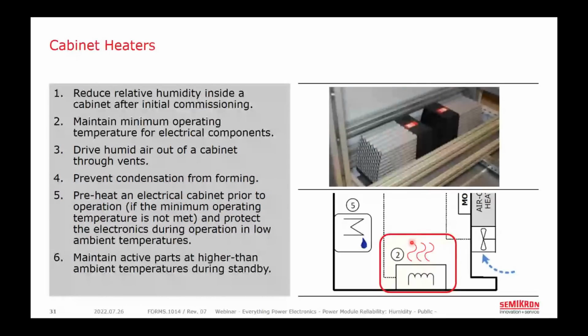And these heaters are also important in making sure that the electrical components meet their minimum startup temperatures in cold climates. Shown here are 2 800-watt heaters in the bottom of a 1 cubic meter cabinet. So this particular setup is designed to quickly raise the internal ambient.